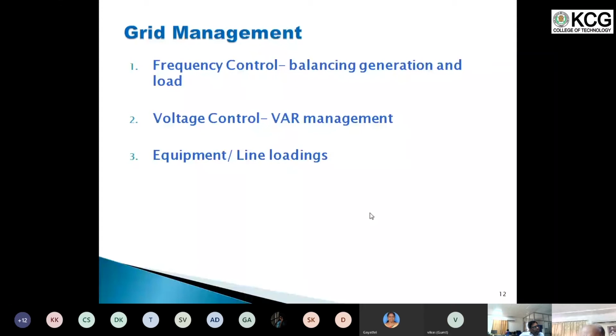You will also have an emergency loading limit available. These are all given in the relevant manuals, that under the normal system you will observe certain loading limits. And when a contingency occurs, we plan our system on an N-1 contingency basis. So if a contingency occurs, if one line is lost, then still, without curtailing any load, the system should not be required to back down any generation or cut any load. That is called the N-1 condition. But there is also a possibility of another element going out, which will be N-2. So for that, emergency loadings are permitted.